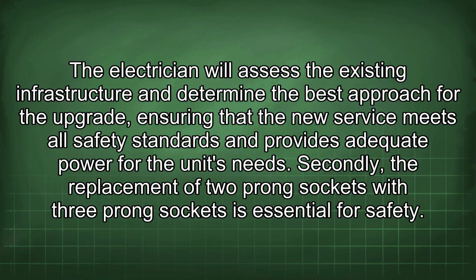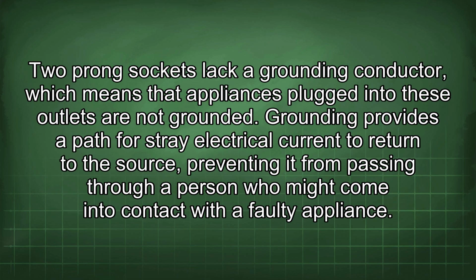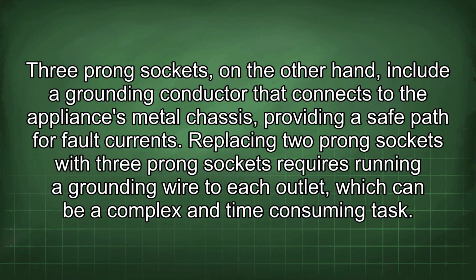Secondly, the replacement of 2-prong sockets with 3-prong sockets is essential for safety. 2-prong sockets lack a grounding conductor, which means that appliances plugged into these outlets are not grounded. Grounding provides a path for stray electrical current to return to the source, preventing it from passing through a person who might come into contact with a faulty appliance. 3-prong sockets, on the other hand, include a grounding conductor that connects to the appliance's metal chassis, providing a safe path for fault currents. Replacing 2-prong sockets with 3-prong sockets requires running a grounding wire to each outlet, which can be a complex and time-consuming task.